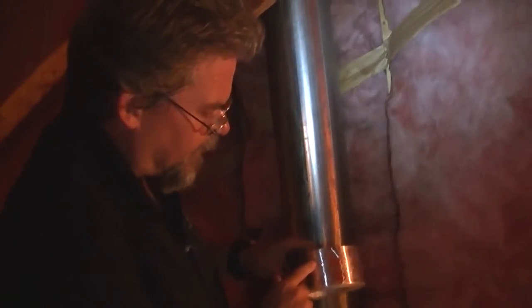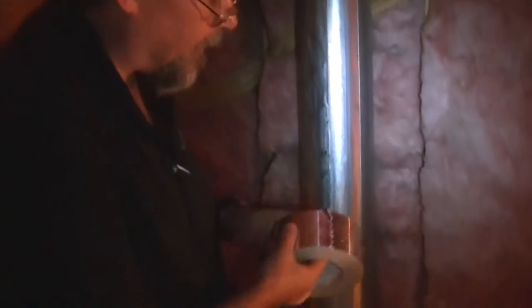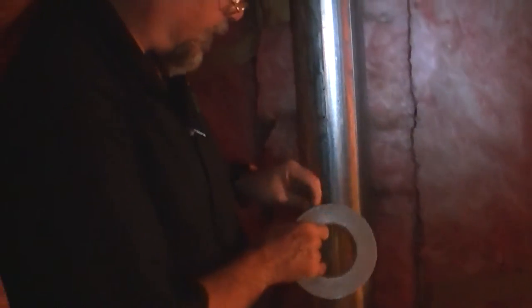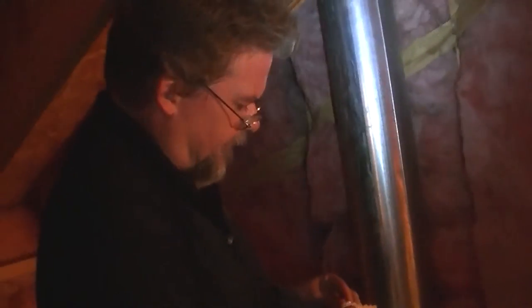We've made a hole in this range hood and we're going to need to close it up. I'm using some tape—I know all tape fails—UL 181A-P, that's duct board pressure sensitive tape, and UL 181B-FX, tape for flex duct. This is a metal duct, but since all tape fails anyway, I'm going to be confident this will work for our purposes today or for sealing small holes like this.